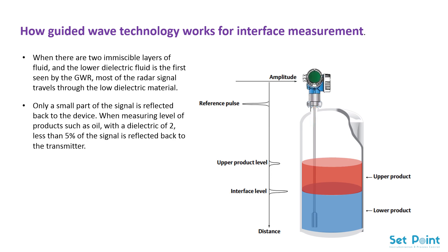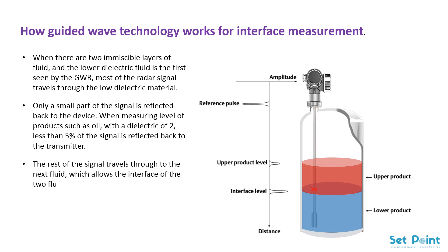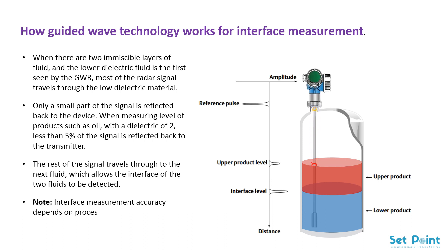The rest of the signal travels through to the next fluid, which allows the interface of the two fluids to be detected. Interface measurement accuracy depends on process conditions such as product dielectric and a distinct interface between the two fluids.